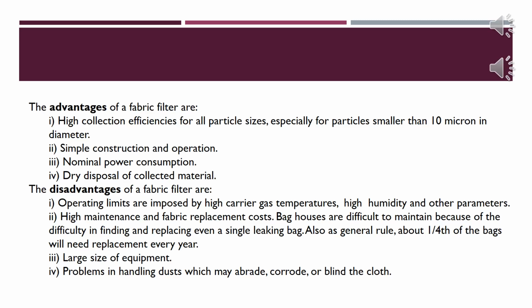The advantages of fabric filters are high collection efficiencies for all particle sizes, especially for particles smaller than 10 microns in diameter, simple construction and operation, nominal power consumption, and dry disposal of collected material.